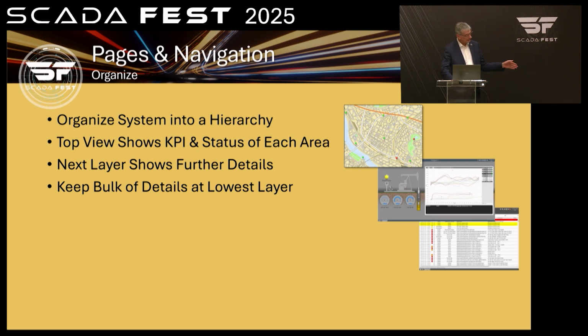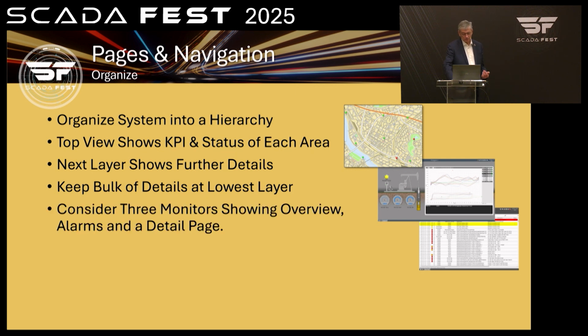Because you can't look at all those lower pages all the time, but you need to be able to navigate to them when there is a problem. So when you click that Go to Alarm Page on your alarm, you get the alarm page, and when you click Go to Page, you can go right directly to the page where that alarm is shown and get more details about everything around that - is the temperature right, is the flow right, is the pressure right?